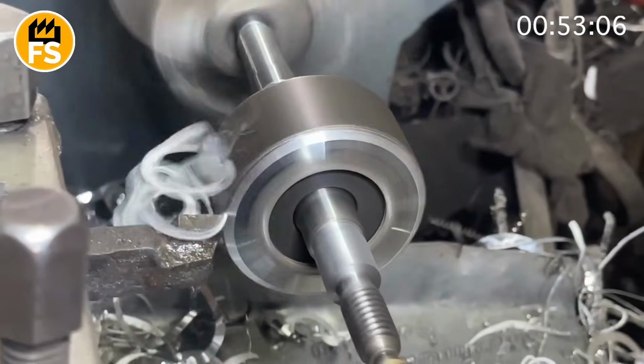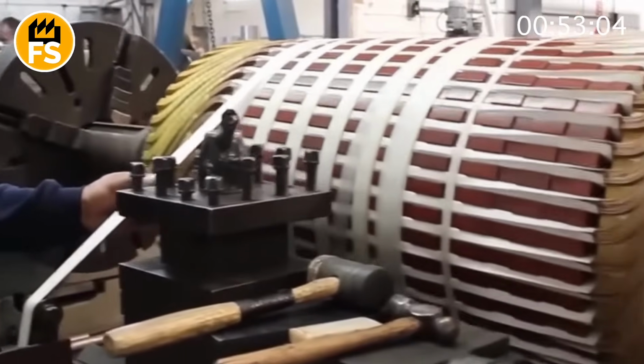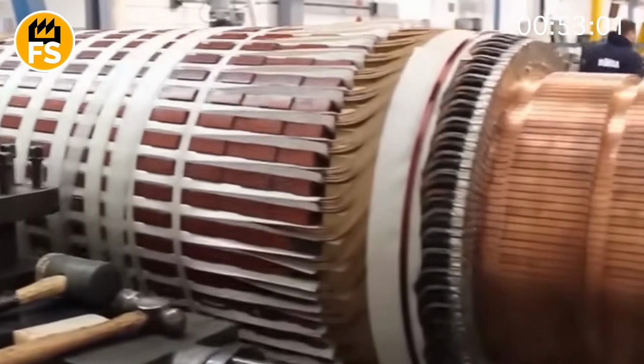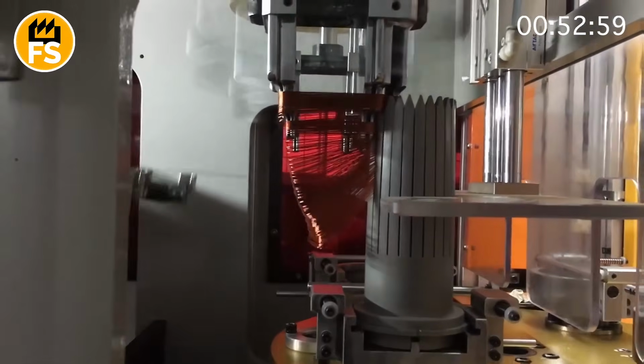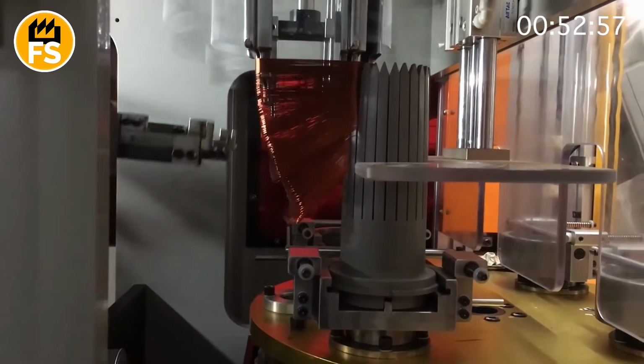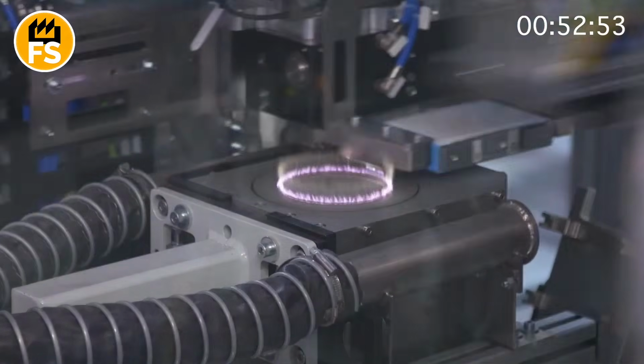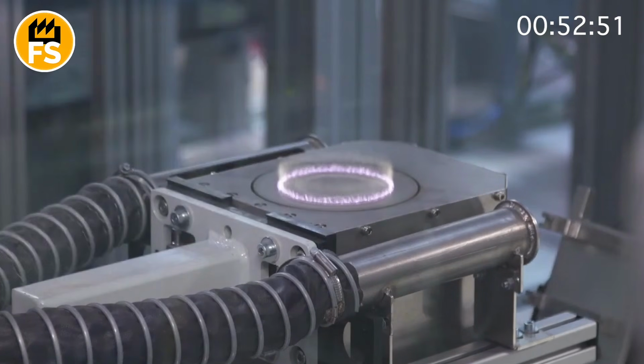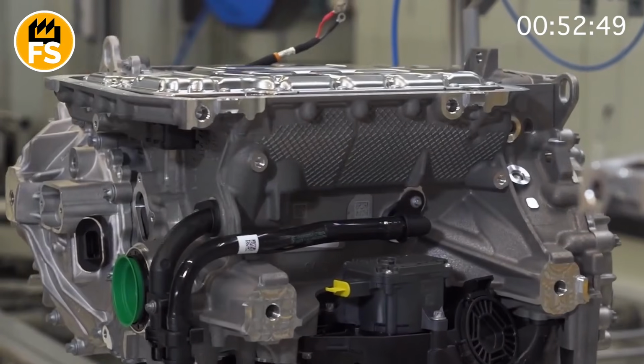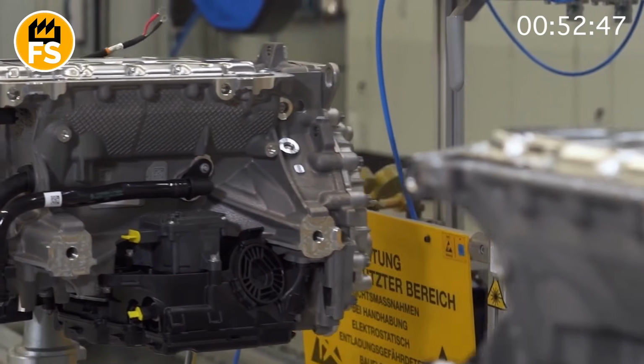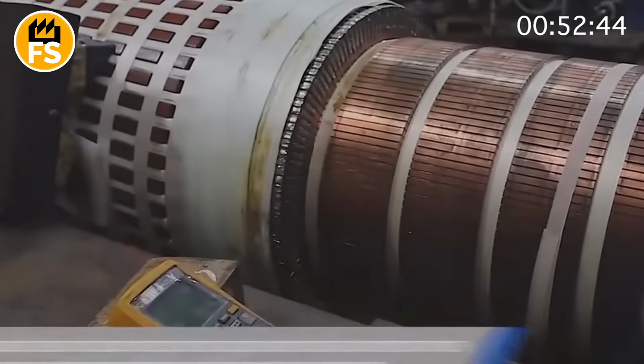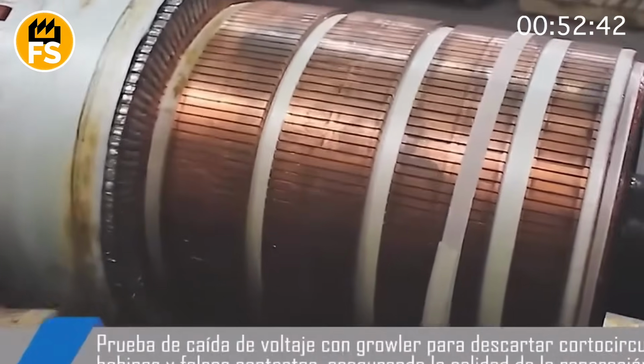But if the motor is more complex, more powerful, then classic windings are used. A worker manually lays copper wire in each slot, carefully tightening it, bending it at an angle. Here, symmetry, precise geometry of the turns, and perfect insulation are important. The wire must lie right, not touching the metal anywhere, not crossing over, not being too tight or too loose. A mistake, and the motor will overheat or fail.